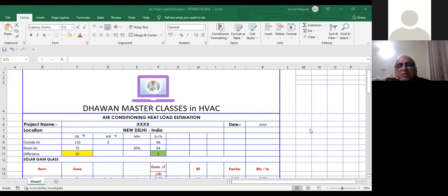it will be used only for the distribution of air inside the room, but it will not reduce the power consumption as a whole. It will add to the power consumption because the heat load of the fan will come from the motor. The ceiling fan motor inside the air conditioned space, that kilowatt will be added to the internal heat source. It may be very minimal, but still it's an addition. It is so small, so negligible, that people just forget about it. It's too small an amount.